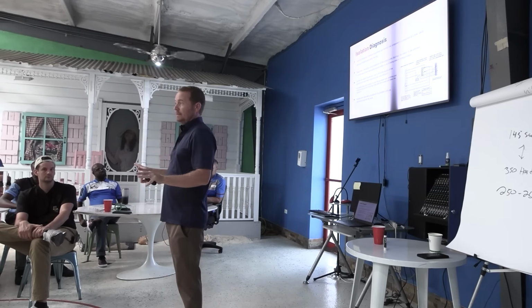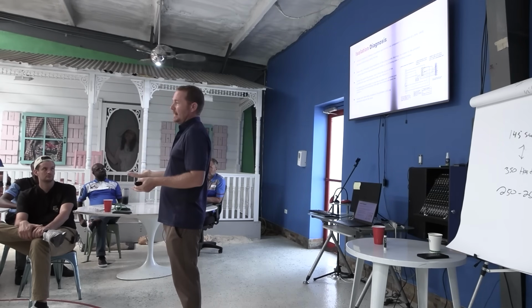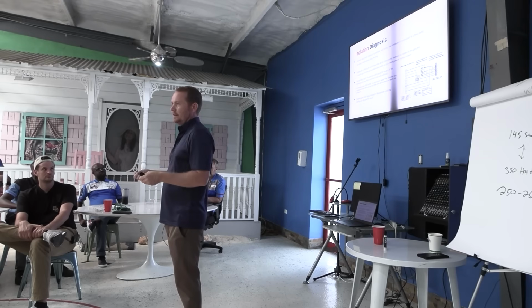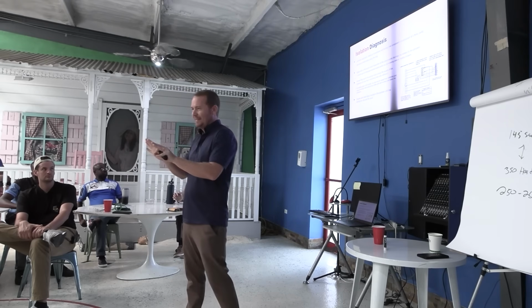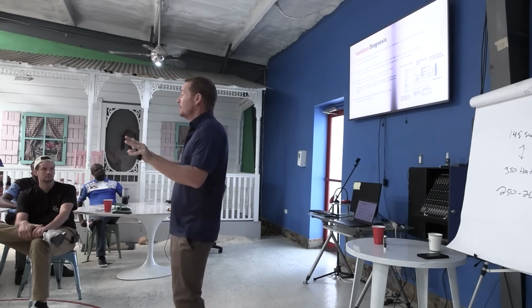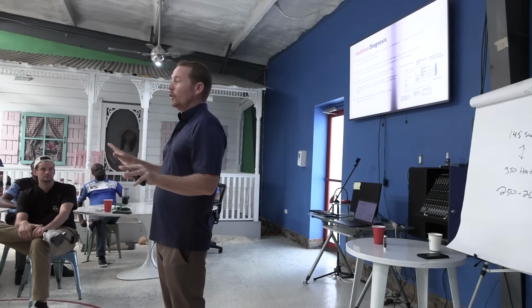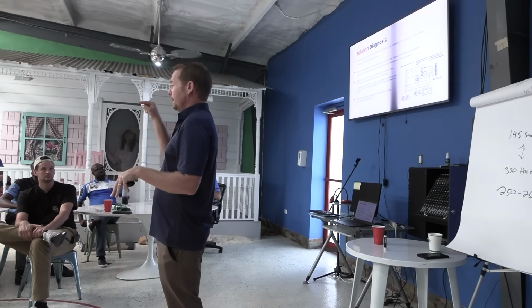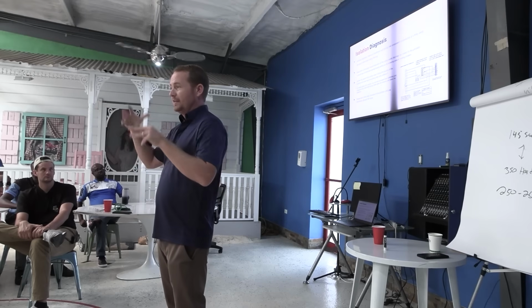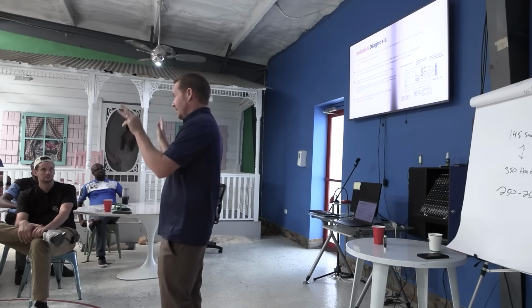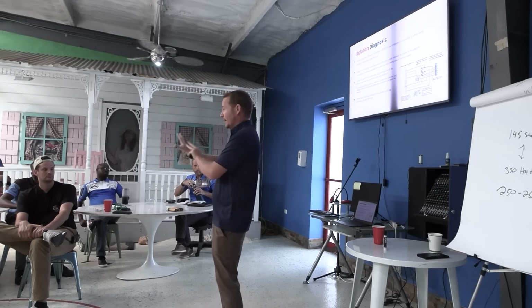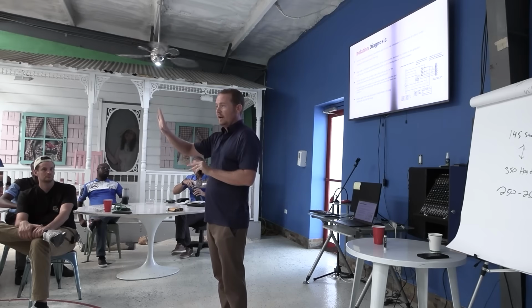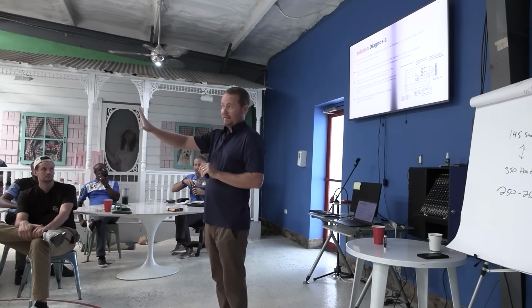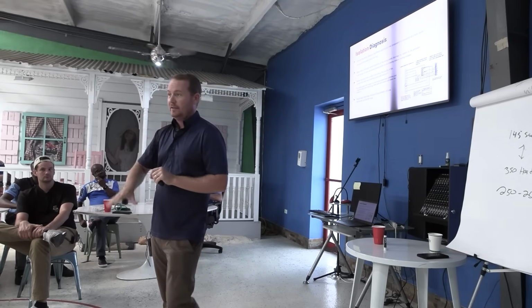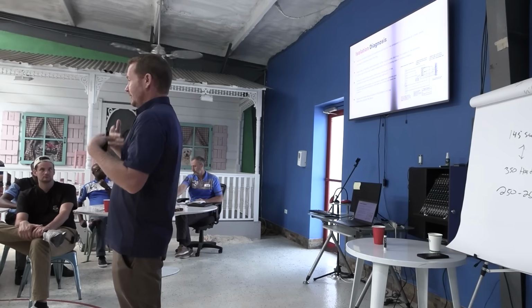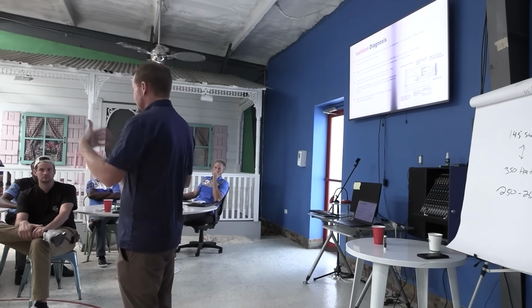Now you know. For more experienced guys who say, well, I just use my ohm meter and I can tell, that's fine, I get that. But for junior guys, trust me, you want them doing that test. You don't want them using some mega ohm meter with a red button that says bad when the compressor's not actually bad. You want them doing what I just said, that final isolation, proving it's just the compressor and nothing else. That's an example of isolation diagnosis.